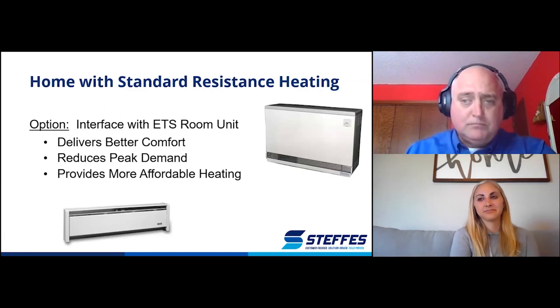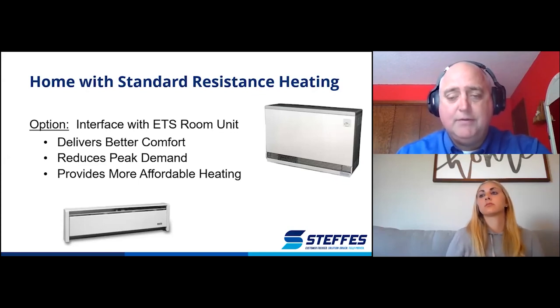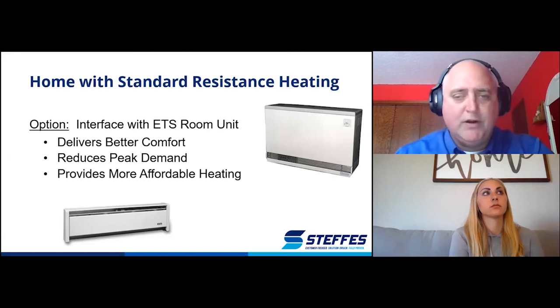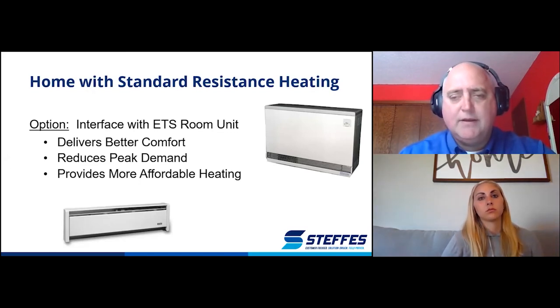Okay, so one of the options is homes that have standard resistance heat and they're looking to heat more affordably; getting onto a time of use or an ETS rate will certainly allow that to happen. So a very common application: we put in 1 or 2 room heaters into the main areas of the home. We leave the baseboards in the peripheral areas, the bedrooms and back areas, and try to do as much work as we can with the ETS heaters, and only use the baseboards or other resistance heat when it is needed. That gets the homeowner on that lower cost rate, but also helps the utility to reduce that peak demand.